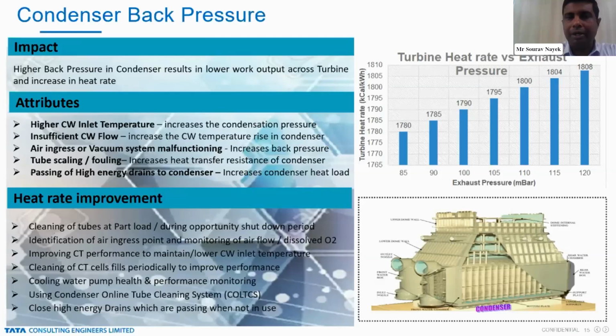Condenser online tube cleaning system is another aspect which will give a preventive measure when the water quality is slightly deteriorated. It will give the cleaning mechanism and it will facilitate the condenser surface smoothness and the heat exchange through the condenser. And last, all the high energy drains should be closed efficiently, so that the excess high energy drains are not coming into the condenser and not increasing the heat load.